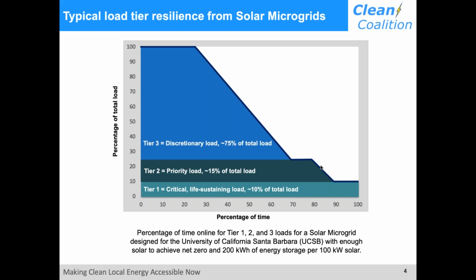We net zeroed the target load, and for every 100 kilowatts of solar, we designed in 200 kilowatt hours of energy storage. If you maintain that 2-to-1 ratio in this part of the world, you get an unparalleled level of resilience. You can keep your tier 1 loads on forever, and tier 1 loads are typically about 10% of the total load.